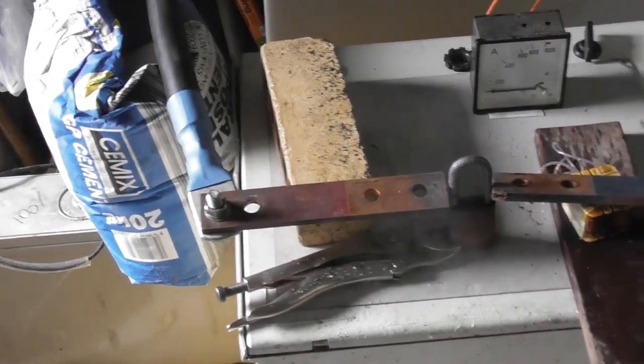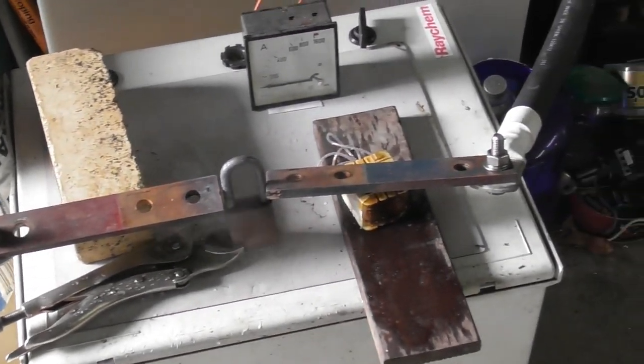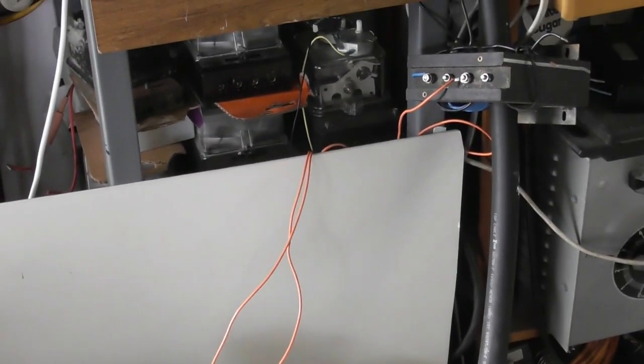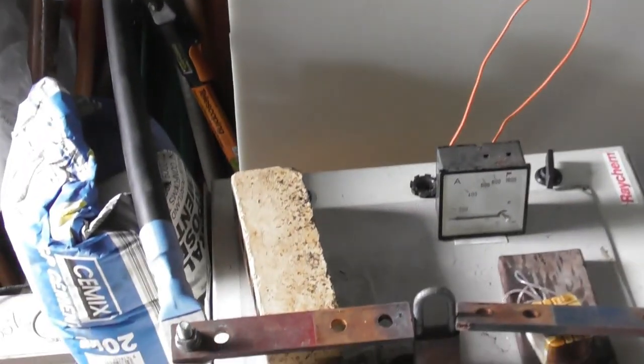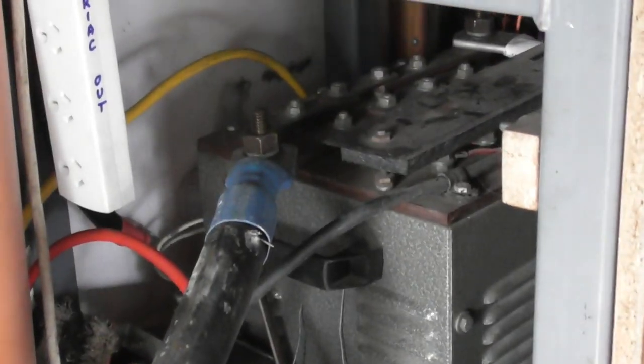The whole setup is pretty straightforward. 300 mil jumpers, copper blades at the end. I don't want to burn the transformer out, which is rated technically for 1,600 ampere for 1 minute, 800 ampere for 2 minutes. And I can smell varnish. So I'll just abandon this. I just don't want to cook this device.